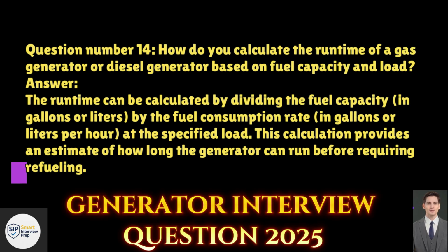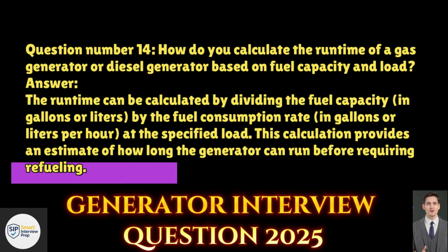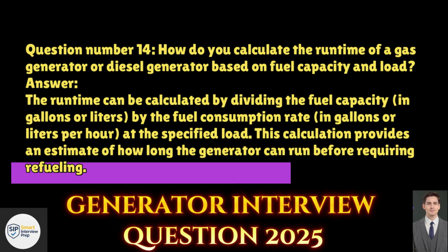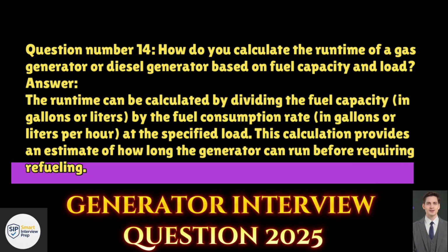Question 14. How do you calculate the runtime of a gas generator or diesel generator based on fuel capacity and load? Answer. The runtime can be calculated by dividing the fuel capacity, in gallons or liters, by the fuel consumption rate, in gallons or liters per hour, at the specified load. This calculation provides an estimate of how long the generator can run before requiring refueling.